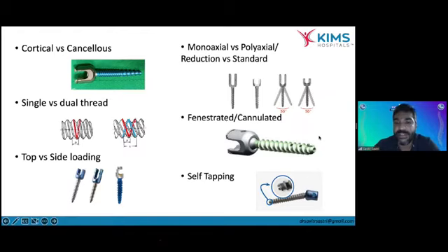Finally, we have fenestrated or cannulated screws. Cannulated screws have a hole running across the length of the screw, which allows for passage of a K-wire through the screw. And fenestrated screws have multiple perforations towards the tip of the screw, which allow for dispensing bone cement. And finally, we have self-tapping screws, where, as I mentioned earlier, the tip of the screw tends to have a fluted edge, so they're able to tap their way into the bone.